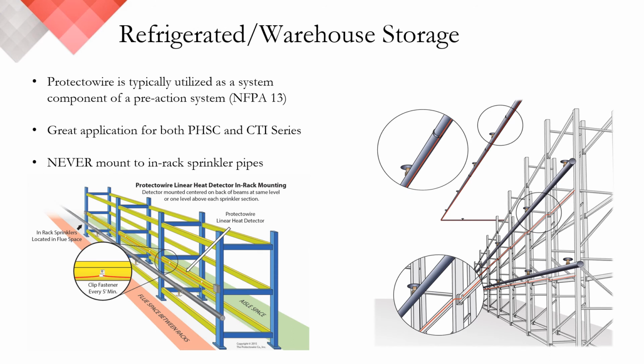One of the most popular applications for linear heat are warehouse storage and industrial freezers. In these facilities, linear heat is typically a component of the pre-action system. In a freezer, it's the primary releasing mechanism for filling a dry pipe system. When installing for in-rack detection, the detector should be positioned in the flue space at the same level or alternating levels with the sprinkler pipe. Typically, and as I've mentioned before, it would be recommended that the detector be fixed directly to the sprinkler if possible and permitted in your jurisdiction. It's still acting as an integral part of the releasing system.